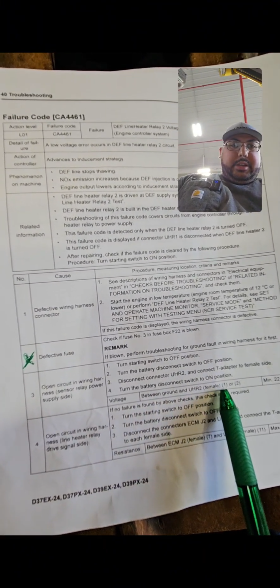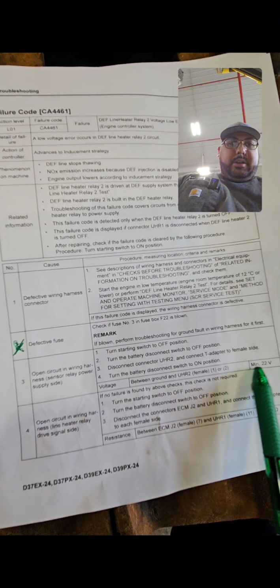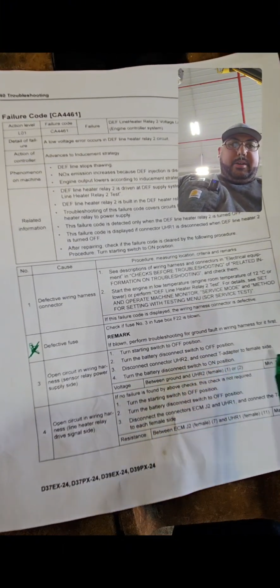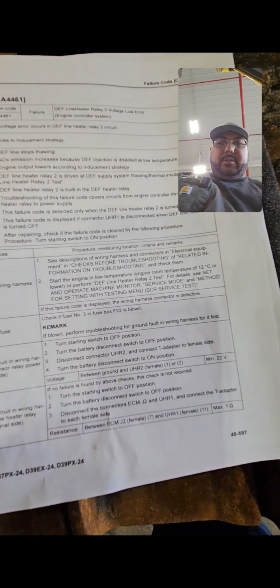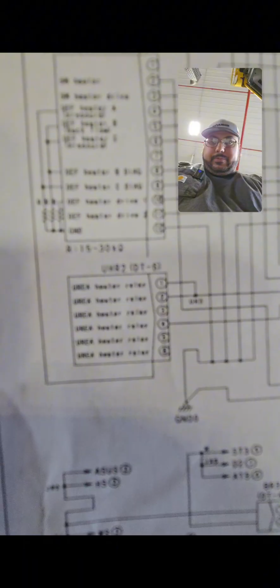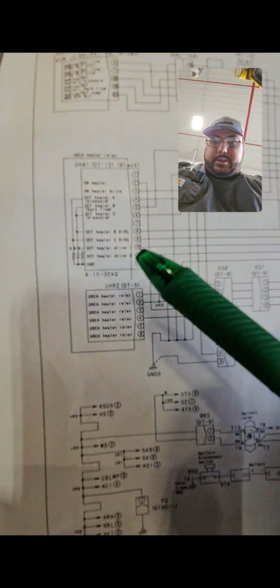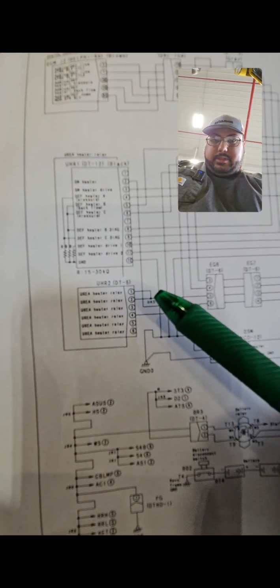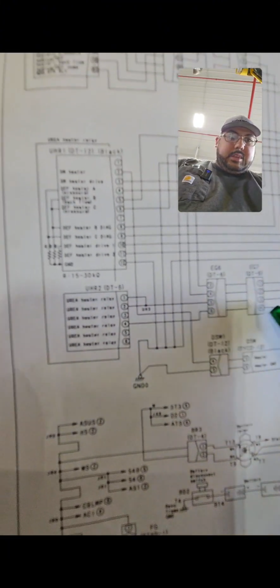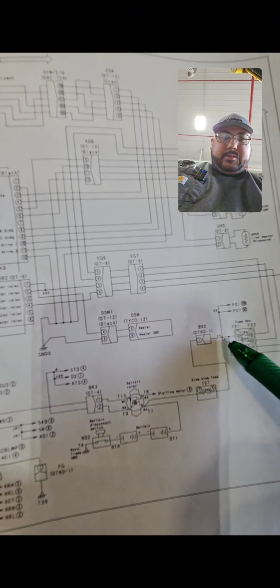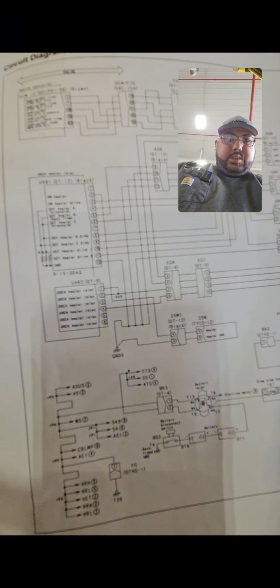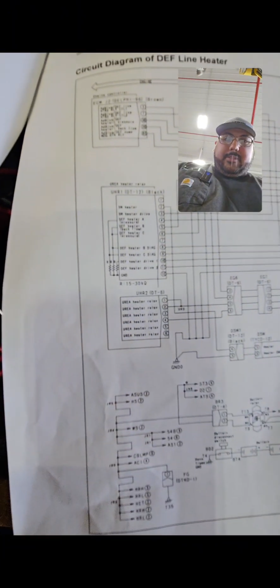So we're going to check between UHR2, female 1 and 2, between ground and female 1 and 2. Should have a minimum of 22 volts. Camera won't focus, but that's between here and here, you see they're tied together there. We went through, followed it, fuse was good, so we know that's not the problem. So we need to make sure we don't have a broken wire over there.